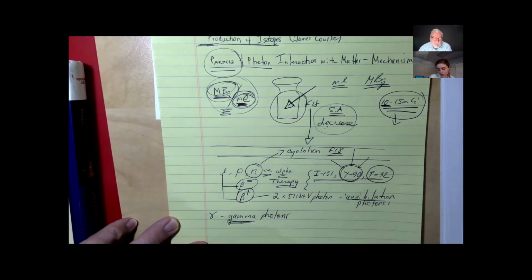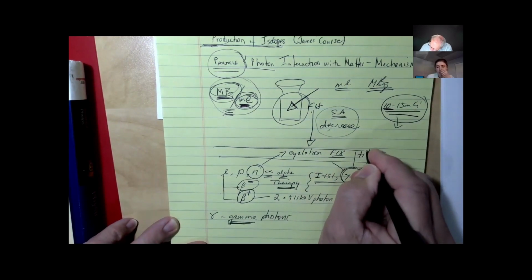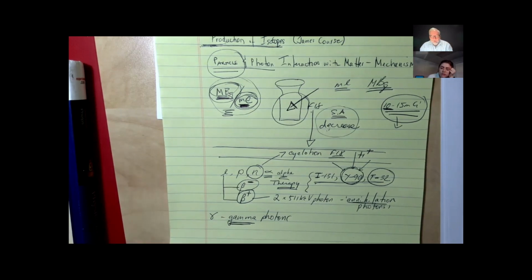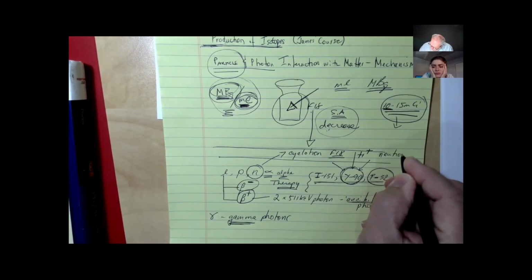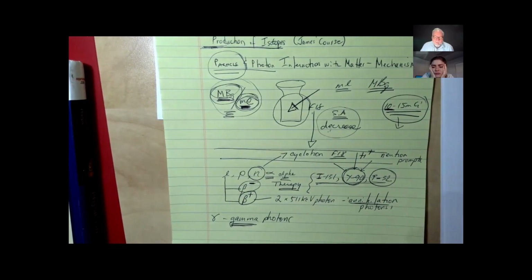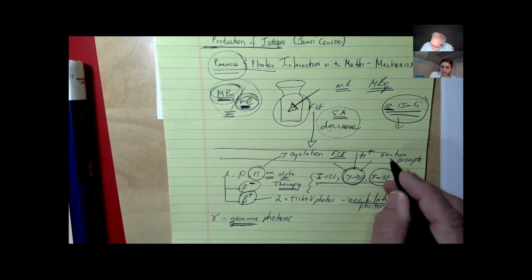During the bombardment, we're irradiating O18 with protons, and in that process you're irradiating not only the O18 water, but the target material and the parts of the cyclotron around that, and you get what we call neutron prompts, because they interact with the atoms that make up the shielding, the walls of the target, and so on, as well as gamma prompts.